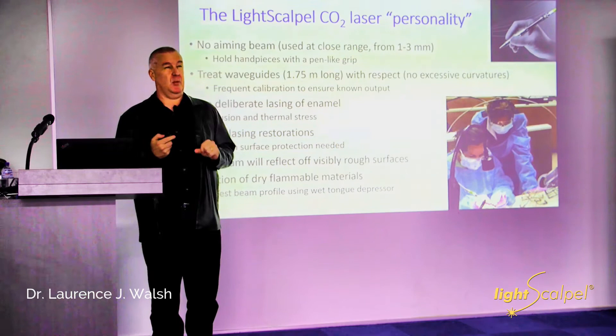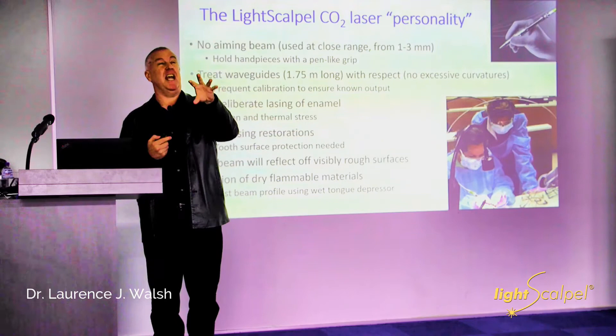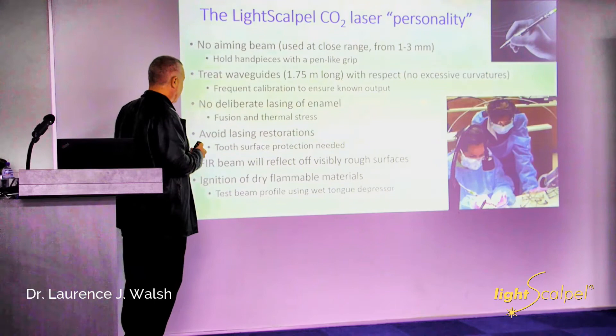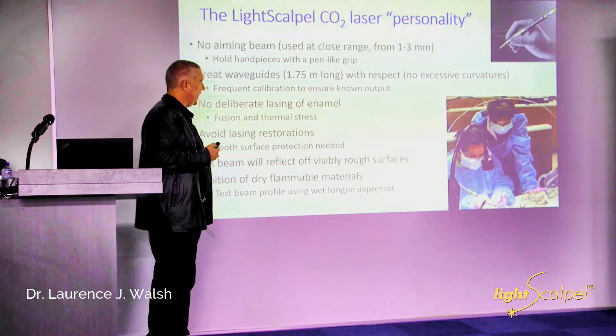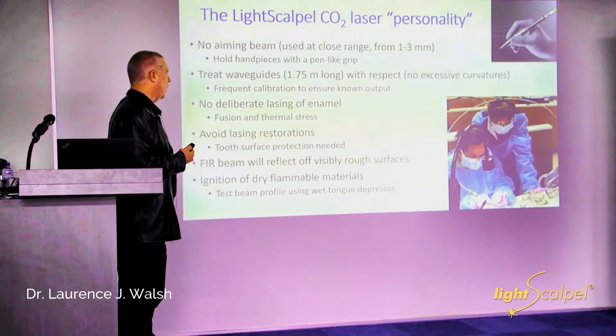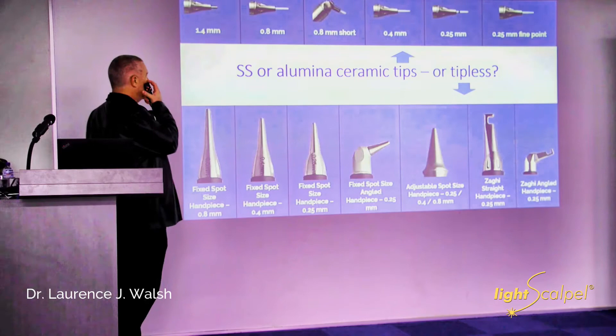Think of it like H.G. Wells' War of the Worlds Martian heat ray — an invisible heat ray that goes from place to place and starts fires. If you're testing the laser on a piece of paper or a dry tongue depressor, it will set it on fire. So we always use a wet tongue depressor, particularly in theatre when checking the laser's performance.